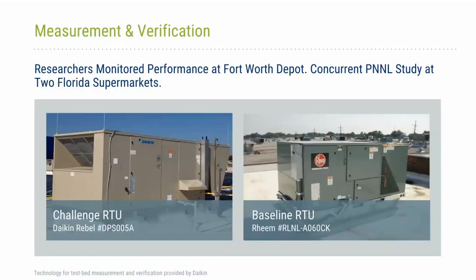So ideally, when you're conducting a measurement and verification process to estimate savings from a retrofit, you want to measure the performance of the existing unit for a period of time, typically 9 months or longer, then replace that existing unit with a new unit. And then develop a model for the unit that you replaced using the monitored data, right? And then you measure the performance of the new unit. So you would then compare the expected performance of the unit that was replaced, that's the old unit, using the model, and then the actual performance of the new unit that you're continuing to monitor in the field.